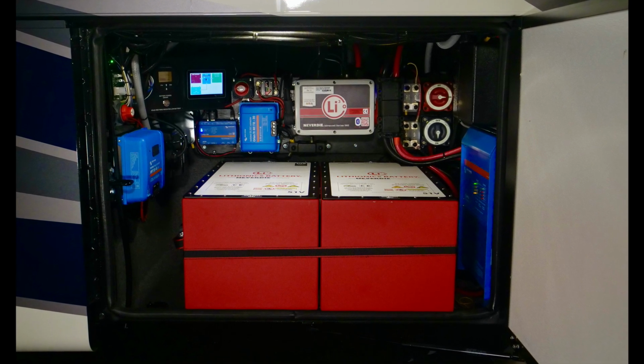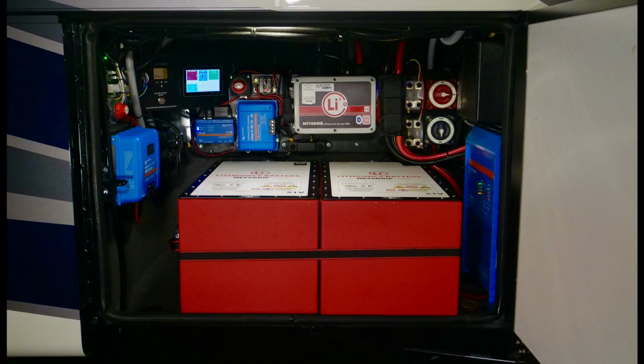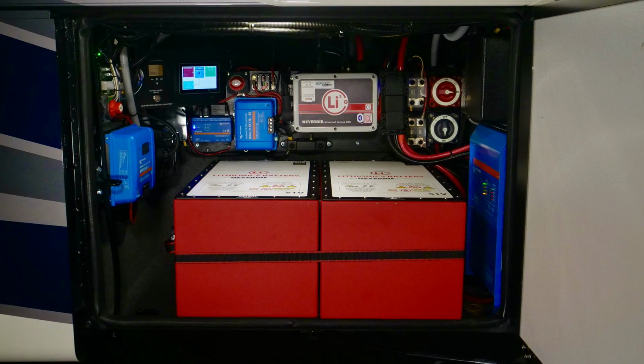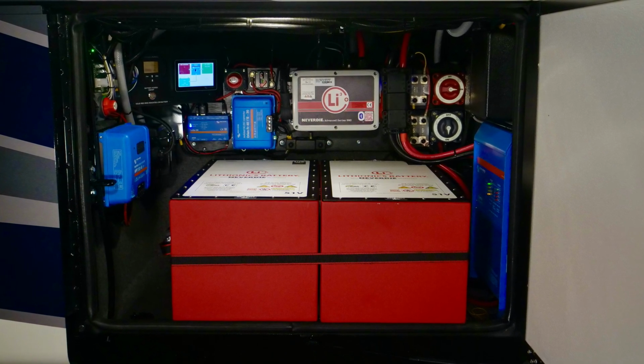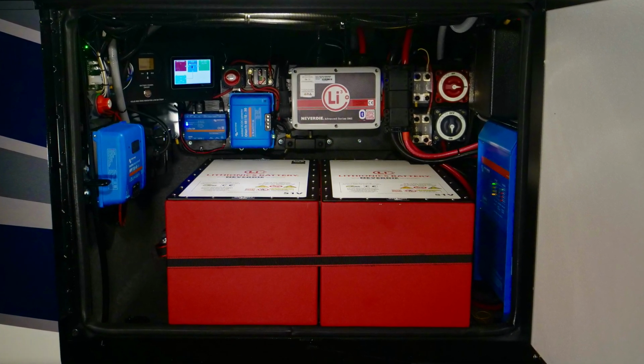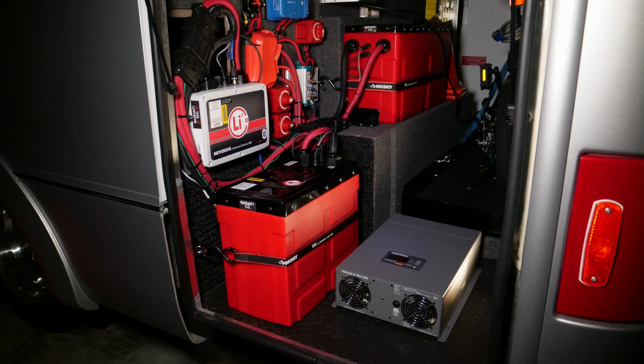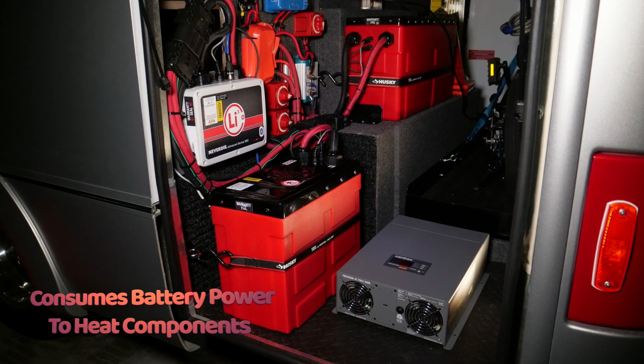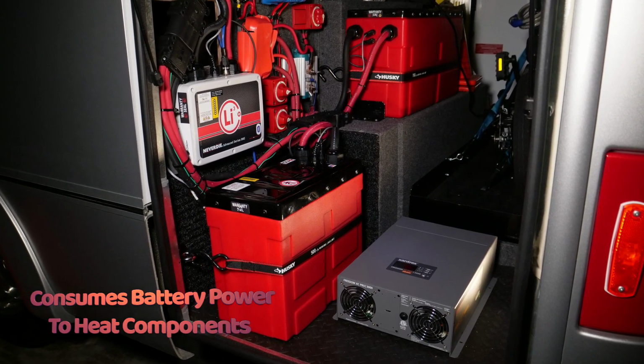In retrospect, this same AC wattage with a 48 volt system would only require 50 amps instead of 200 amps, and the fuse holder and wiring would remain cool to touch. Keep in mind it takes considerable battery power to heat large cables, fuses, and terminals, which all reduce battery capacity.